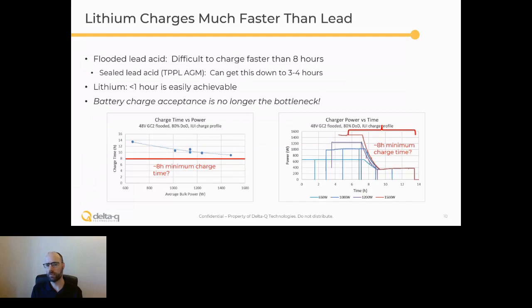What you're seeing at the bottom is some data from my lab, where I've taken a 48 volt flooded lead acid golf pack, discharged it to 80% depth of discharge, and charged it with a standard 3-stage or IUI charge profile. You can see from the plot on the right that the first stage is full constant current or constant power, the bulk phase. Then there's a constant voltage stage, so power tapers down as the current tapers down. And finally the third stage is called finish, which is a lower constant current.